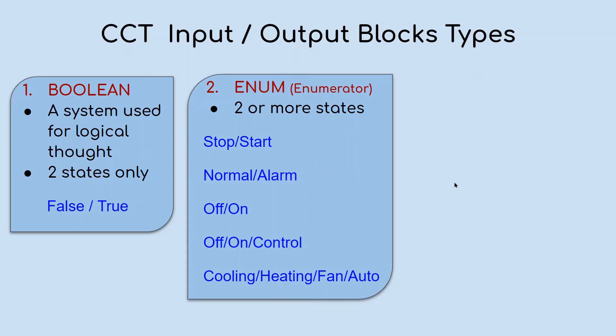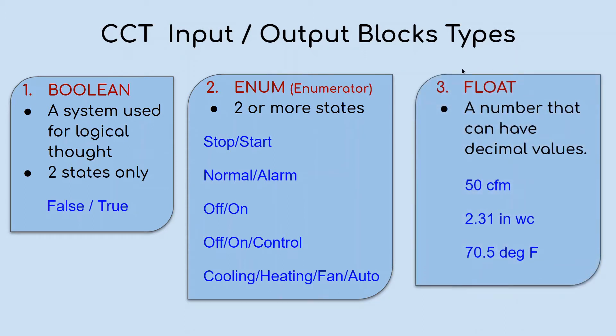The second type of inputs or outputs is Enum, short for Enumerator, and this means two or more states. An input can have either off/on, normal/alarm, or more than one state — for example: off, on, control, cooling, heating, fan, auto. The last type is Float, which is different from Enum and Boolean as they are numbers — numbers that can have a decimal value, can be whole numbers, or negative numbers.